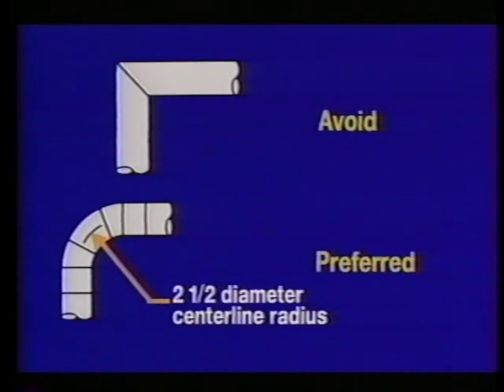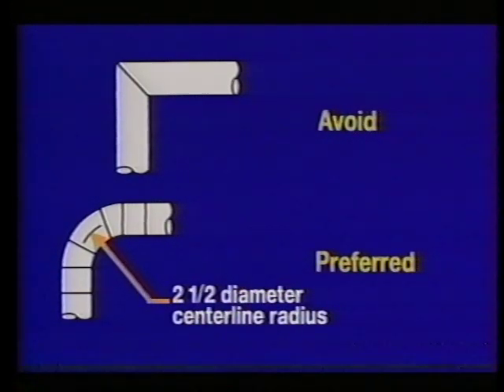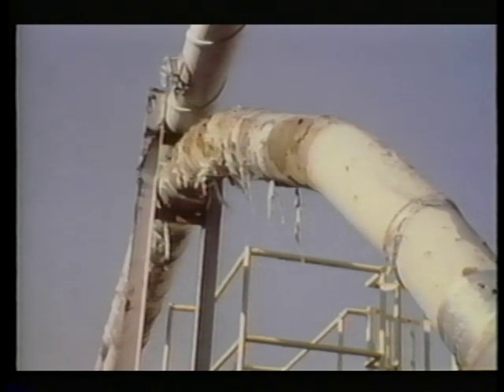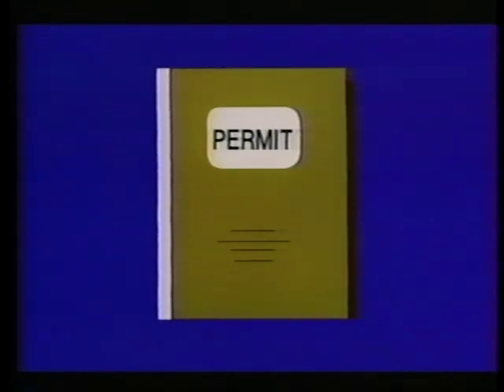Avoid two branches entering directly opposite each other to reduce turbulence loss. Avoid sharp elbows such as a mitered elbow. The magnitude of pressure losses caused by elbows depends on the radius of the elbow curvature compared to the duct diameter. Where space permits, elbows should have a centerline radius of two to two-and-a-half duct diameters. Replace ductwork when it wears out due to erosion and impact damage from airborne particles, and maintain all ductwork in good working order. During design, remember to check with your local air pollution control agency to obtain a permit — the agency can give you guidance for selecting an air cleaner.